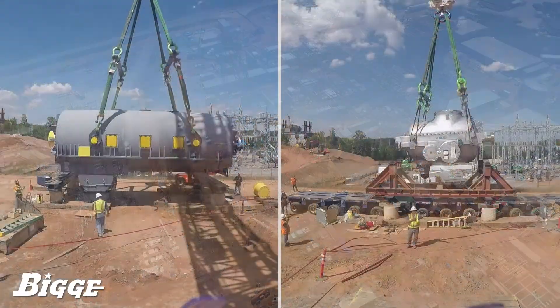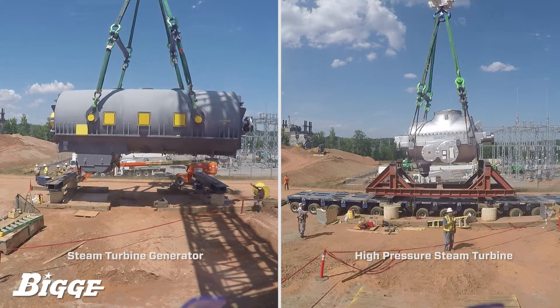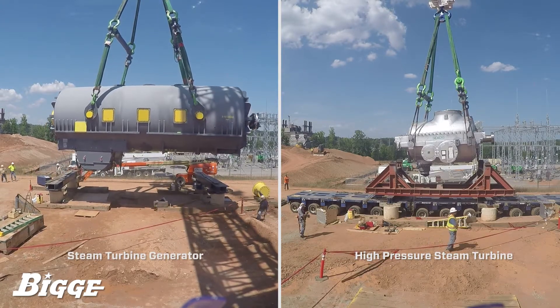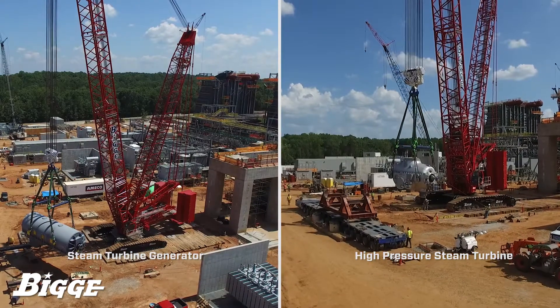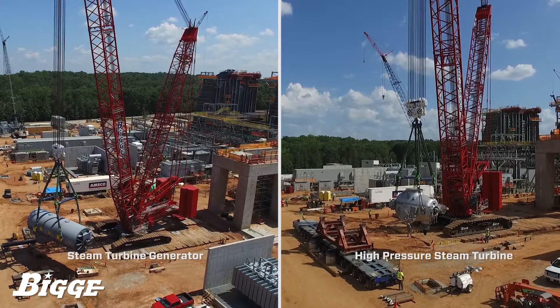In July of 2016, Bigge executed the lift of steam turbine components at a combined cycle power plant in South Carolina. Employing a Manitowoc MLC-650, a steam turbine generator and a high-pressure steam turbine were successfully lifted and rough-set at a total combined weight of 595 tons.